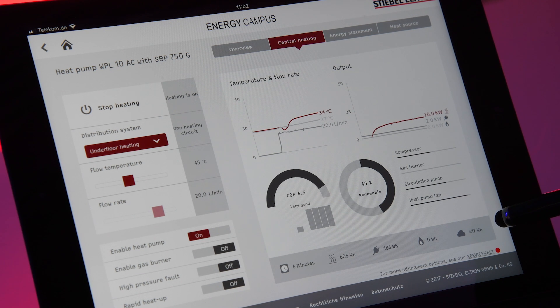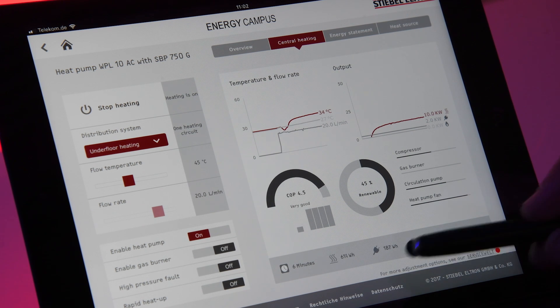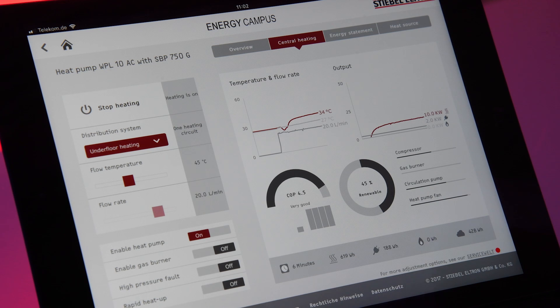413 watt hours we have taken out of our source. So 187 Wh (electrical) plus 413 Wh (from source) gives us the 600 Wh of heat produced, and this gives us an overall efficiency — a COP of 4.5 at the moment.